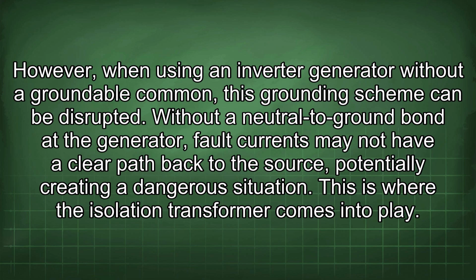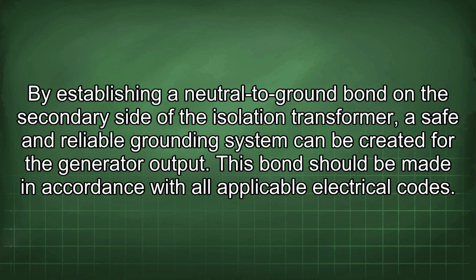Without a neutral to ground bond at the generator, fault currents may not have a clear path back to the source, potentially creating a dangerous situation. This is where the isolation transformer comes into play. By establishing a neutral to ground bond on the secondary side of the isolation transformer, a safe and reliable grounding system can be created for the generator output.